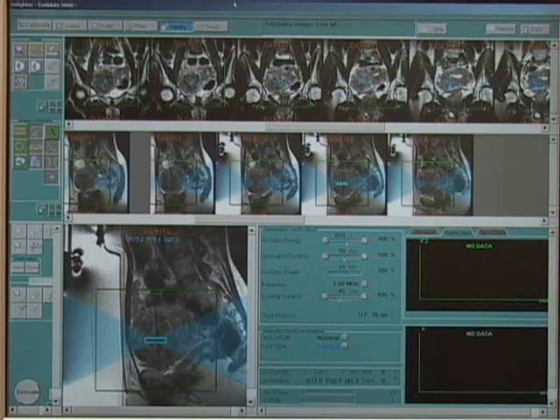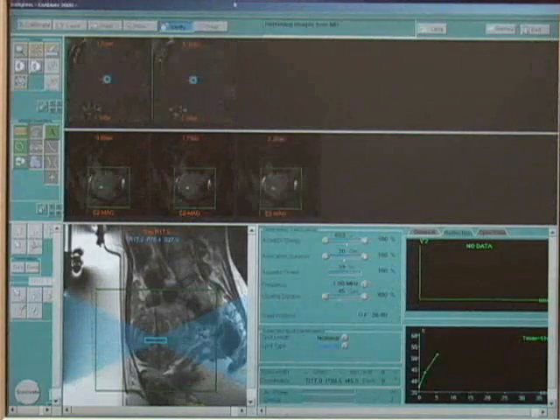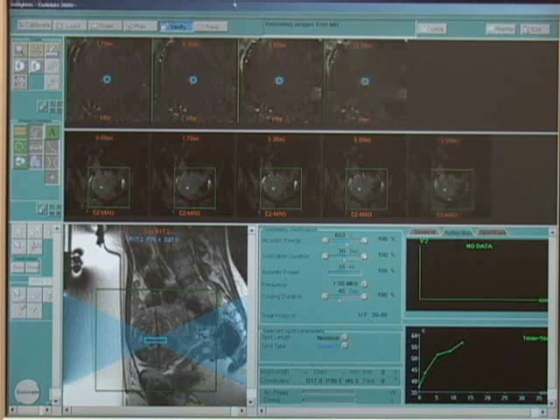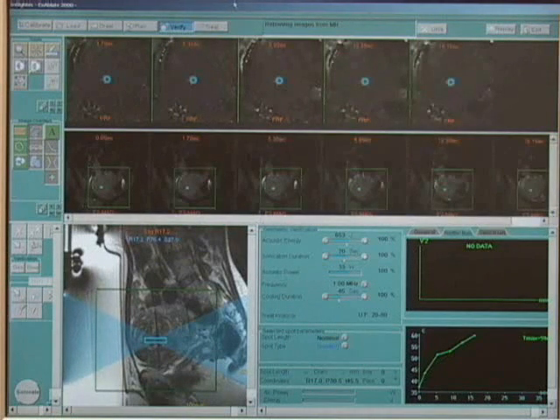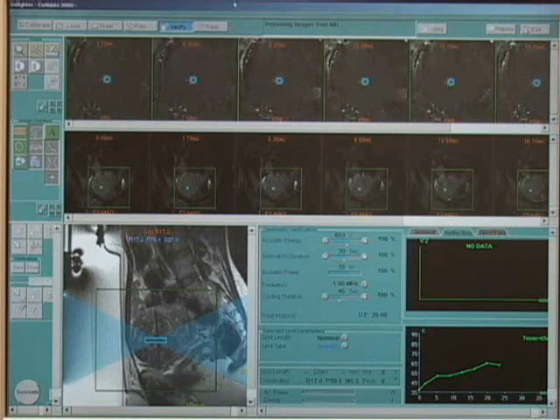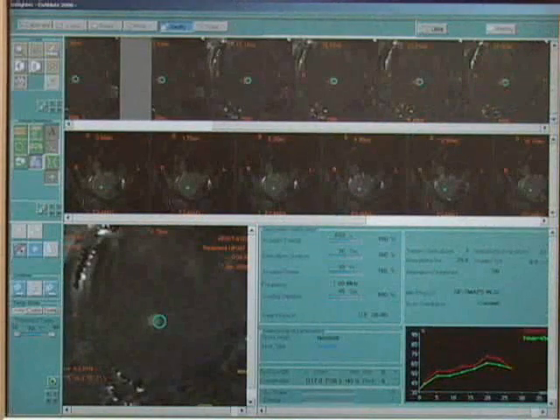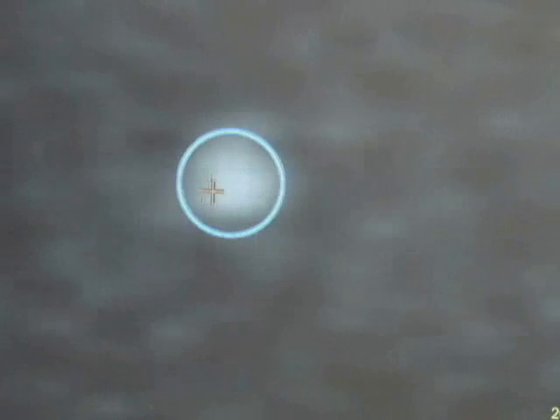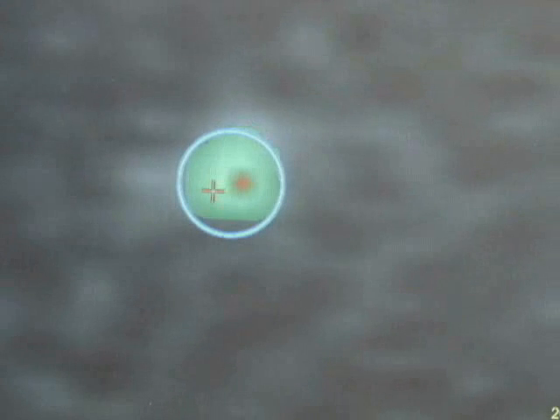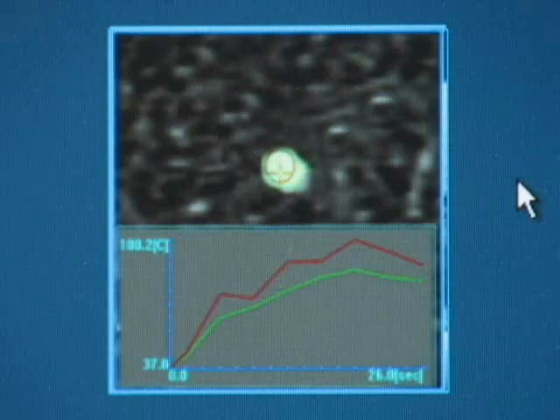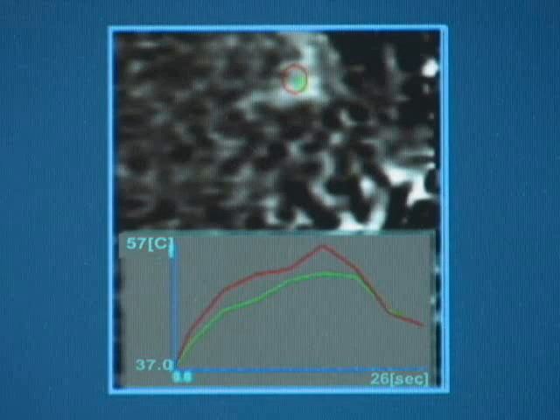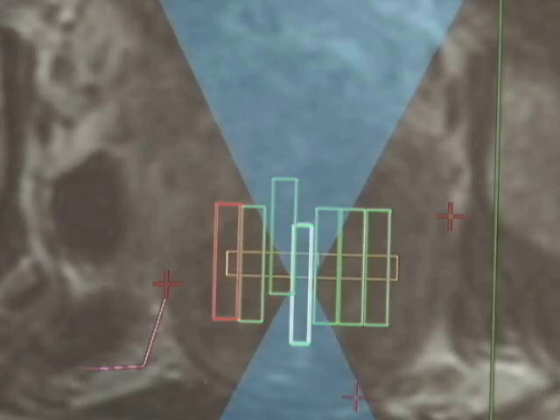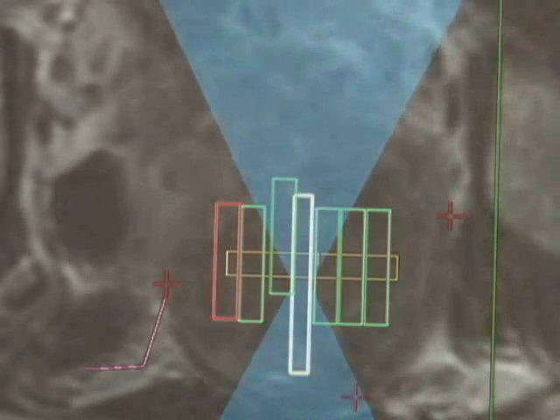Thermal imaging is used to verify system calibration and dose suitability. First, a low dose of energy, too low for necrosis, is used to identify the actual point of energy delivery and adjust small beam deflections caused by patient-specific tissue deviations. Next, a full dose of energy is used to verify that the planned dose reaches the 65 to 85 degrees needed for thermal ablation. This confirms that the energy selected is neither too hot nor too cold. If so, adjustments are made. At any time, parameters can be altered to obtain the desired results.